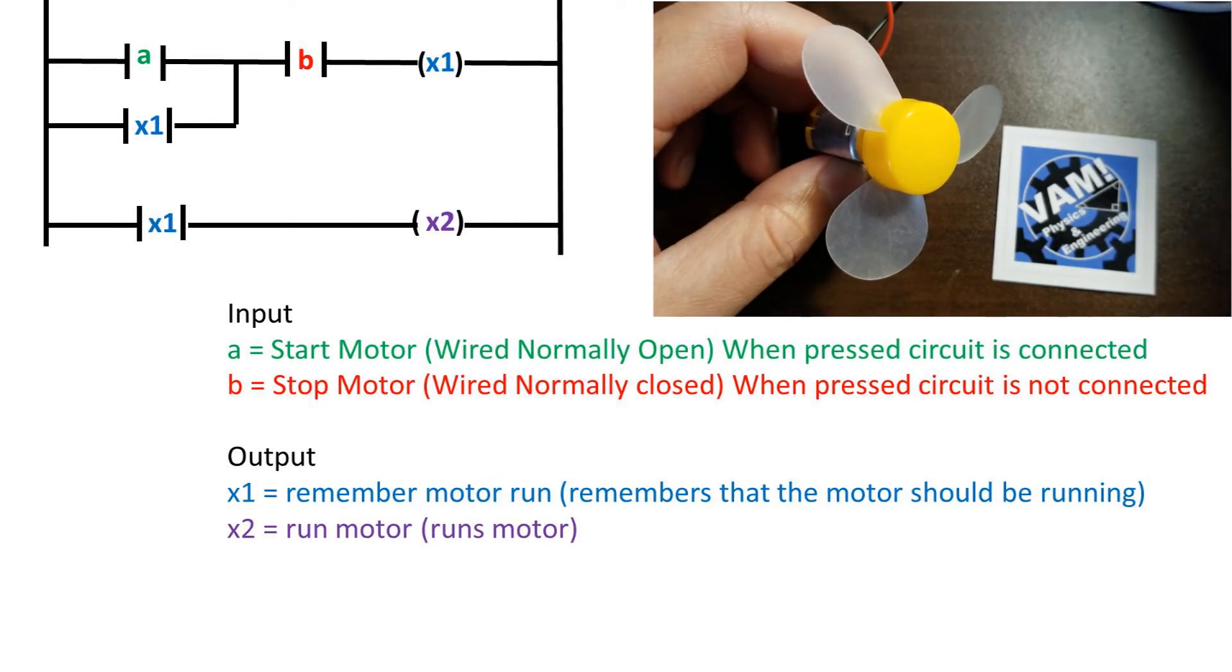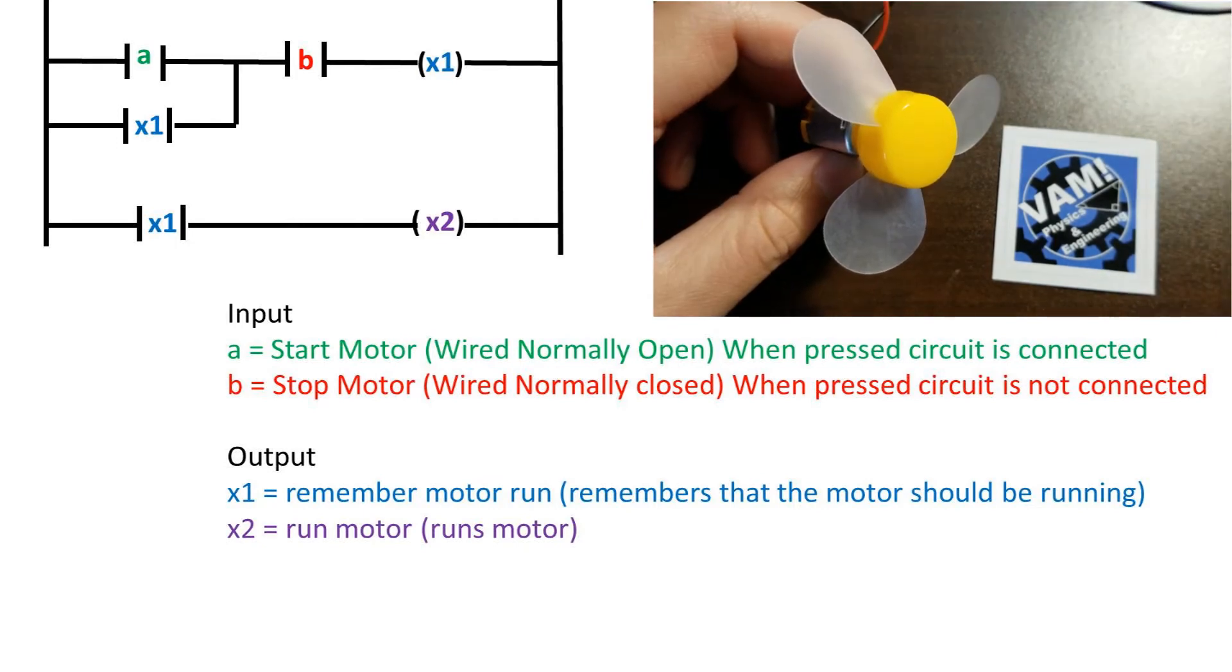We put that same bit in parallel with the start button, or in other words, OR-ed, so that either the start button can be pushed, or it can remember that the start button was pushed, and the motor will run. We then place another rung that has a contact of X1 that, when activated, completes the circuit and powers on the motor, which is coil X2.